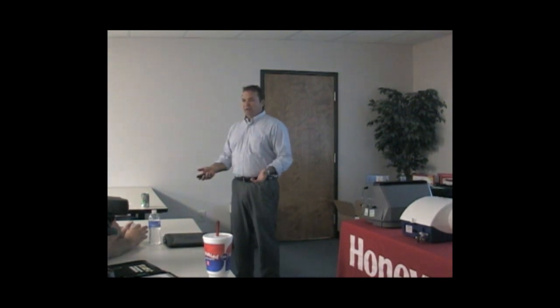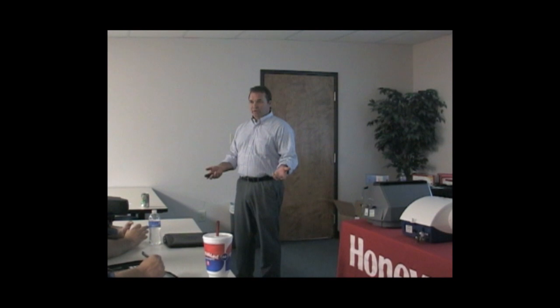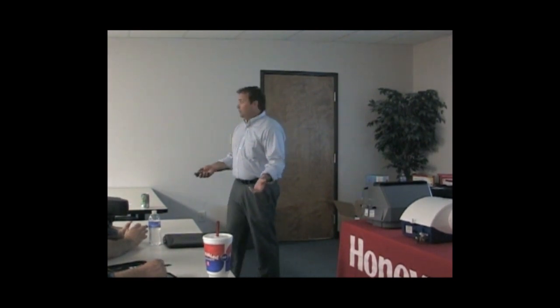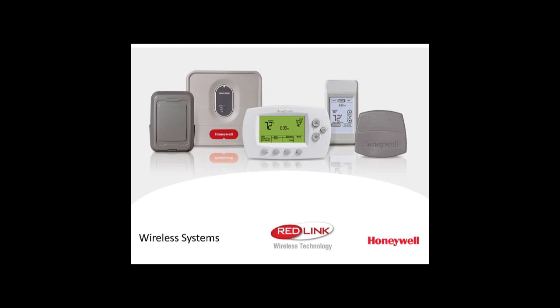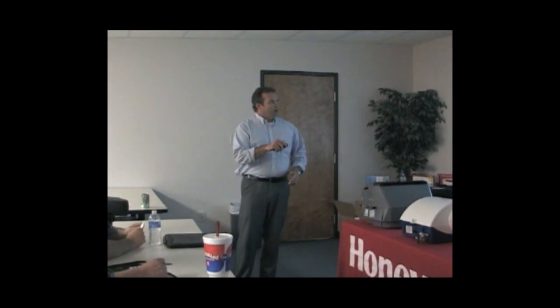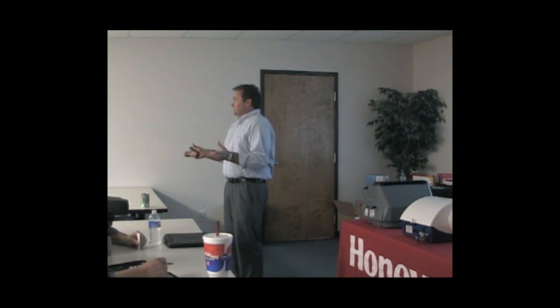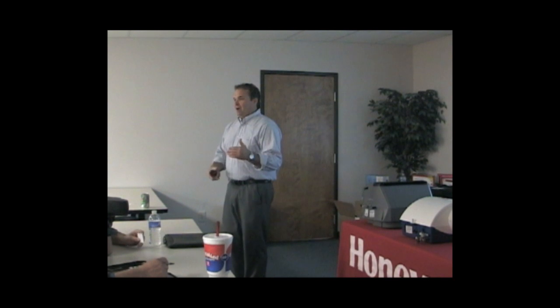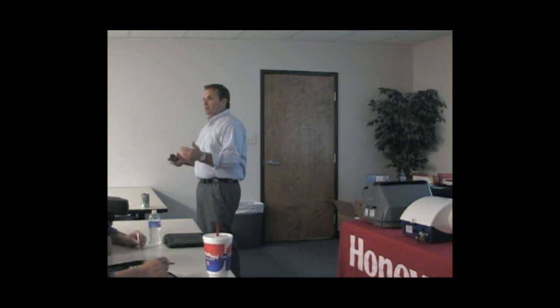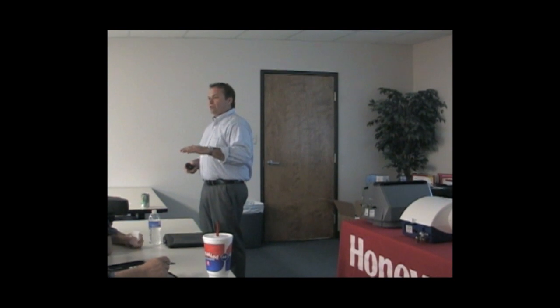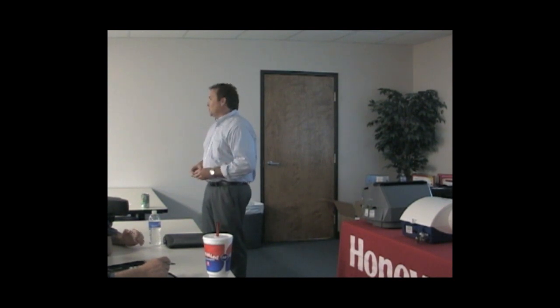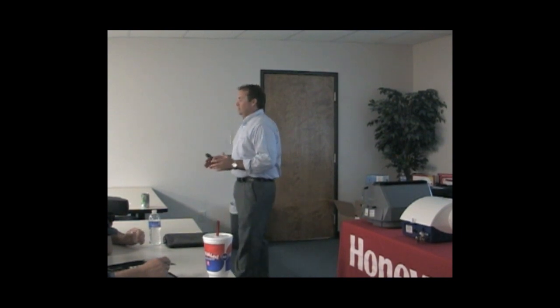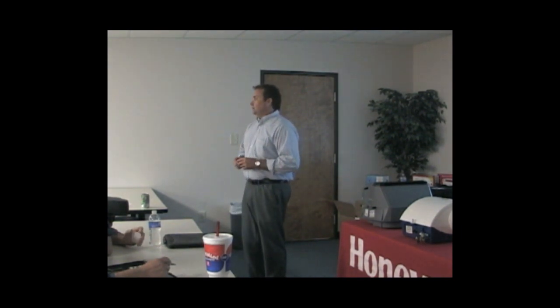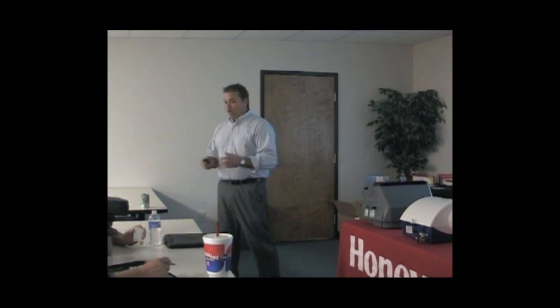Well, what happens if the battery dies and that thermostat or something goes wrong with it? I have no heat, I have no cooling. So with these systems, we have return air sensors that come with them, so if I lose signal of that stat, it's going to start a 30-minute timer on this board that says, I haven't seen the thermostat, what's going on, let's start a 30-minute timer. After 30 minutes, if it still doesn't see a thermostat, it'll never let that house get colder than 62 or hotter than 82. That's a benefit to your homeowner, that's better than a wired stat, and doing that alone helps you give more value to your customer.